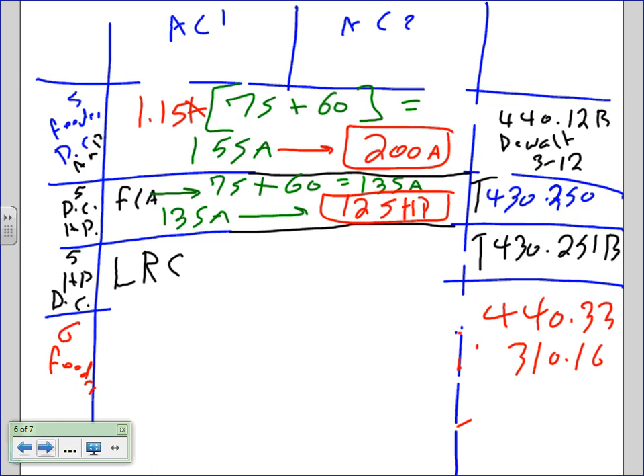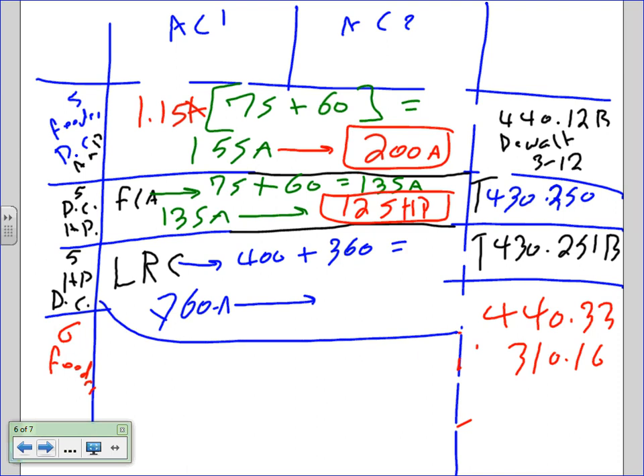Let's go to the second horsepower rating. The second horsepower rating, guys, is locked rotor current. Locked rotor current, I have 400 given plus 360. That will translate into 760 amps. Take it to table 430.251(B), and that will translate again into 125 horsepower. So William, we need to choose the largest between 125 and 125.